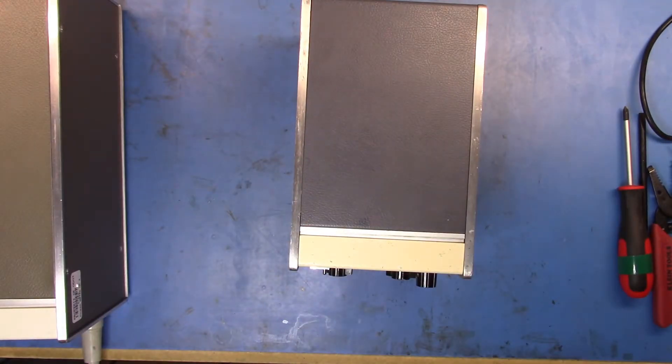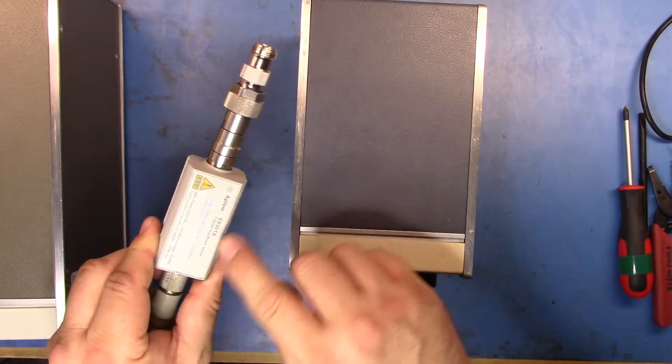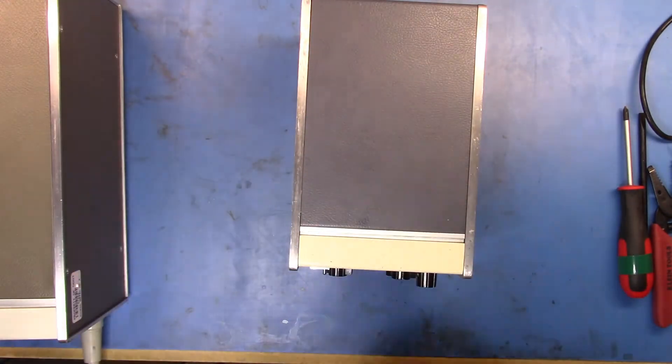And they're a different type of sensor than the one that you would get, that you've probably seen before, which is the thermocouple, the diode version. And they're an open-loop system. So you need to be able to have an accurate measurement of the reference level that's actually on the meter. And that's how you typically do it, is with one of these types of meters.